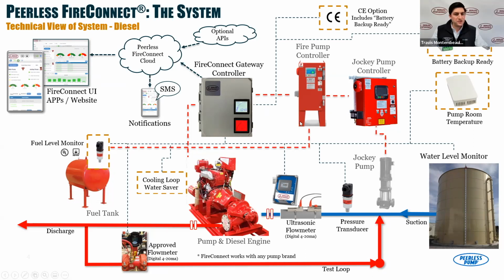I guess a couple other notes on this system. I mentioned connecting to the fire pump controller and the jockey pump controller. These controllers are Modbus enabled and give us the data that we need. Typically you're picking up your core mandated dry contacts from your fire pump controller: phase failure, phase reversal, main switch off, whether it's electric or diesel. You're taking the four critical ones, and a lot of times they're picked up through the building management system or a remote alarm panel, depending upon your jurisdiction.